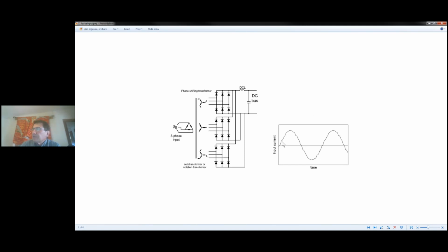Now, by the way, this is roughly how your input current looks with an 18 pulse setup. And that is a picture of the 18 pulse system at rated load. We know that because it's a passive filter, it doesn't react to conditions, and as you change the load and change the speed, which on a centrifugal pump are coincident events, you will get less and less performance as you come off of the optimum design point for this passive filter. But the main point is parallel diodes versus series diodes, and you don't want to discover that at installation time.